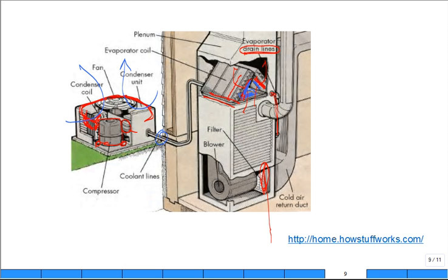The other thing that will happen is if it mats up, it'll get so cold in some sections it ices up. And when it starts to ice up, you get ice buildup on your coils. So there's a lot of bad consequences to not having good filters that you repeatedly change out when they start to get full, because you really want to protect your A coils. And then there's the blower, the fan, that provides the movement for the air.